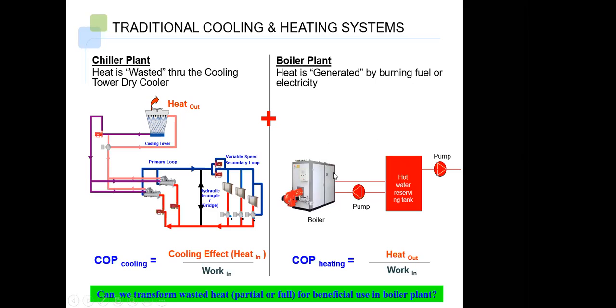While in the boiler plant, we are firing a boiler, we are burning the fuel and generating the hot water. So here we are giving the energy, and in the chiller plant, we are rejecting the heat to the atmosphere. So the idea in the heat recovery is, why not we use this heat output for effective utilization for the hot water system? Why do we waste it? I'm saying instead of generating fresh one. So typically the COP of a chilled water plant is cooling effect over work done by the compressor. And in the boiler plant, the heating COP is heat output over how much work in has been given.